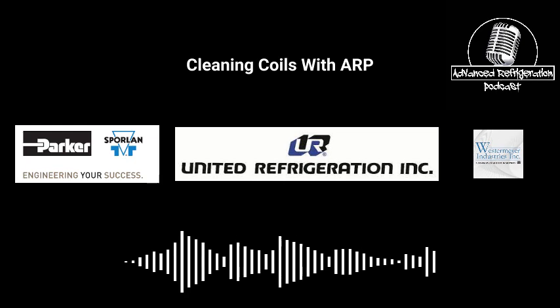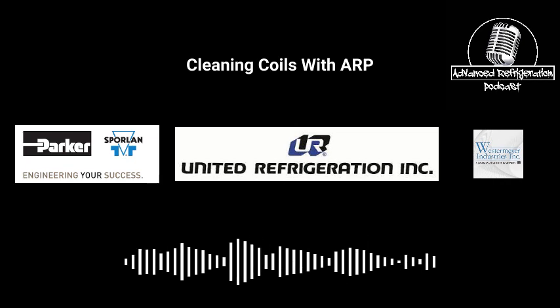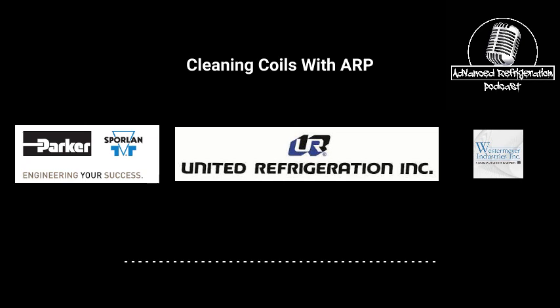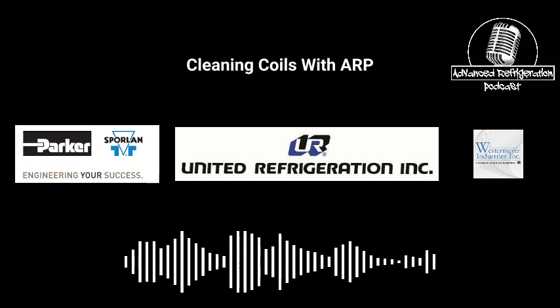Generally, if you're on a supermarket roof and somebody didn't make the dumb decision to put the bakery hood or an exhaust hood right next to the condensers, because there's a million other places they could have ducted it, you should not have grease on condensers where you need coil cleaner. You should be able to just clean the condensers. But like I've said, if somebody let them go and they push it up in there, you're going to need chemical. So be aware of that and make sure the chemical doesn't affect that roof.